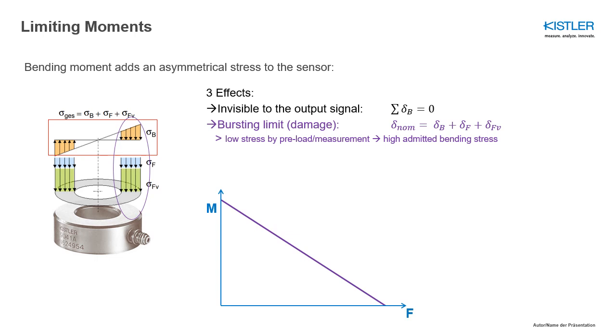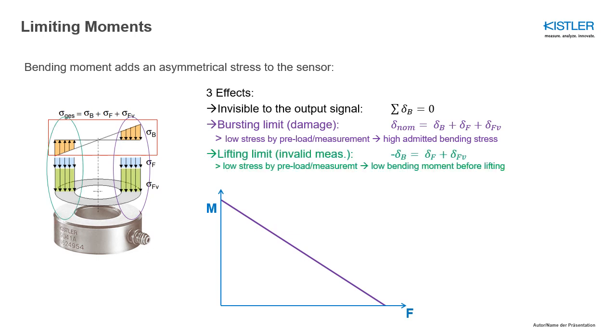Second point is the bursting limit. A bending moment adds some stress on one part of the sensor, and since you can't see it, you might go above the nominal load that is allowed for such a sensor, and you risk to damage it. You can see it here on the graph below, where we have two axes, force and moment. And as you can see, the more moment you have, the less force you're allowed to apply, or vice versa. That means the closer you come to the nominal force of your sensor with your process, the lower is the allowed bending moment.